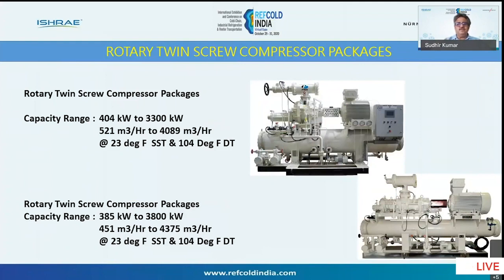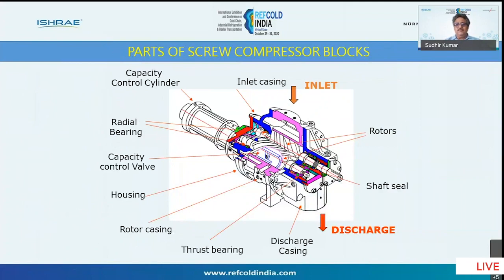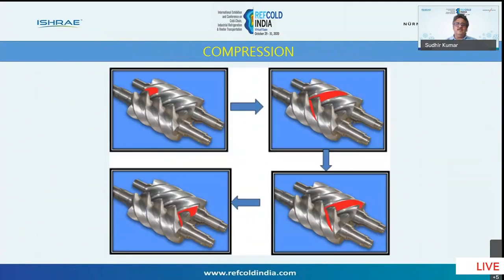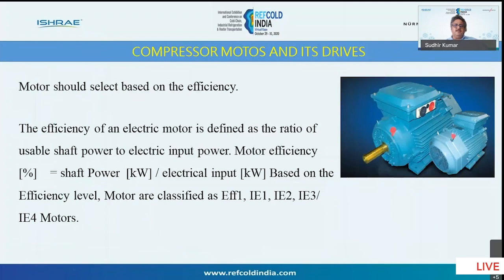So screw compressors have various advantages. One is it's got fewer moving parts, and plus it is running at a very high RPM, which is approximately 3000, 3500 RPM. So for the same capacity, the plant room size becomes smaller. And also, this is how compression works in a screw compressor. Between the male and female rotor, the gas, the red color one, which is shown in the slides, is how the gas is compressed from the suction to the discharge. So it is directly coupled to the motor running at approximately 3000 RPM.